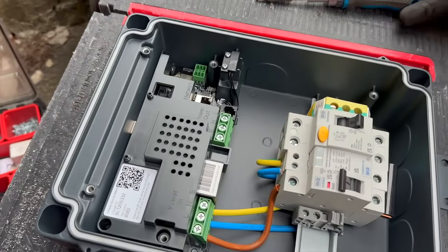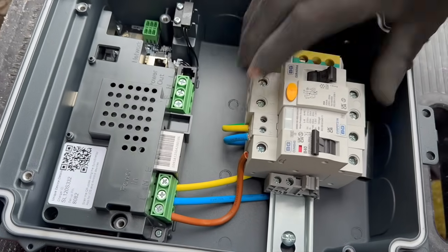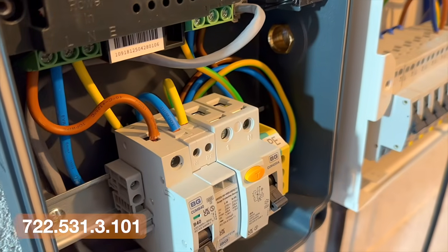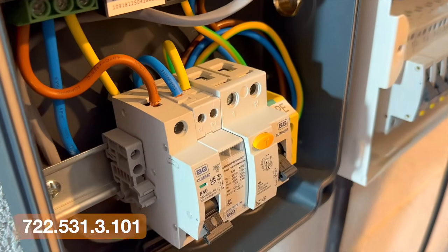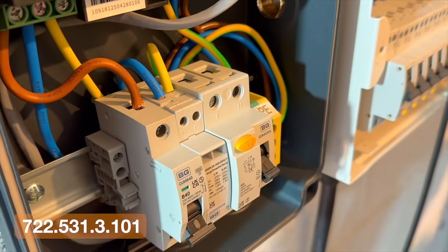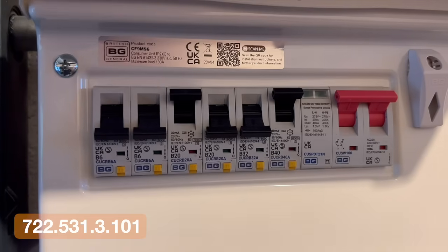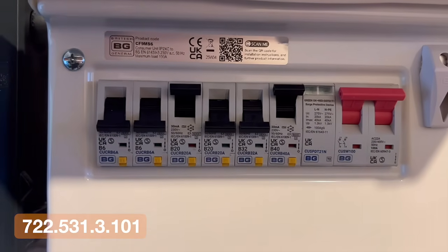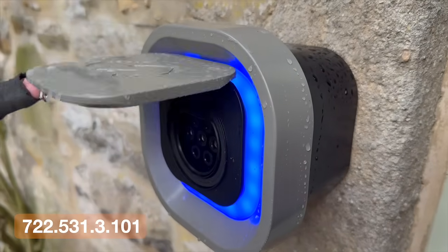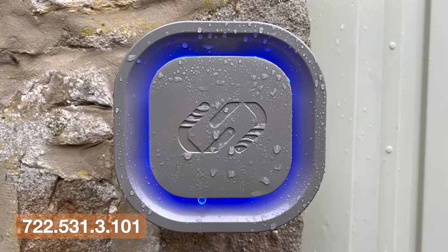EV charging has had some important clarifications that will affect how you design and install these circuits. One of the biggest changes is the recognition of RCDs incorporated within the EV charger itself. Regulation 722.531.3.101 now formally recognises these devices, in particular devices that provide both AC and DC protection within the charger, often referred to as RDCPDs. This is a big shift because previously there was a strong push towards installing external Type B RCDs. Now, if the equipment complies with the relevant standard, that internal protection can be relied upon.